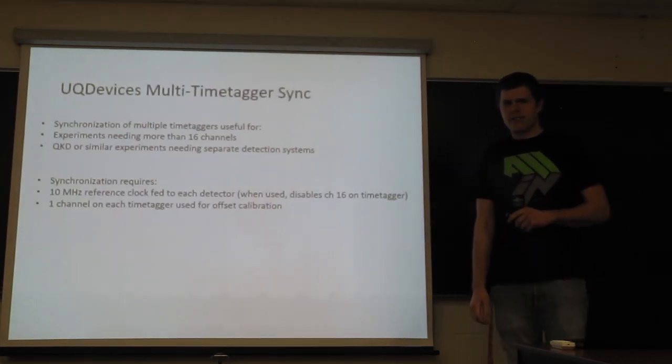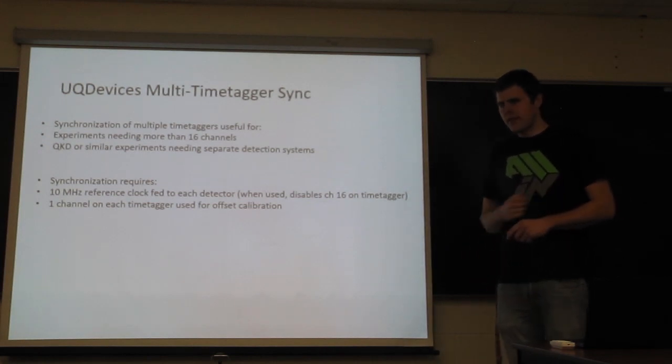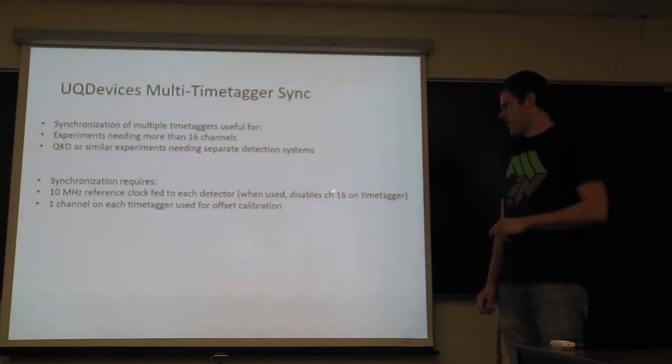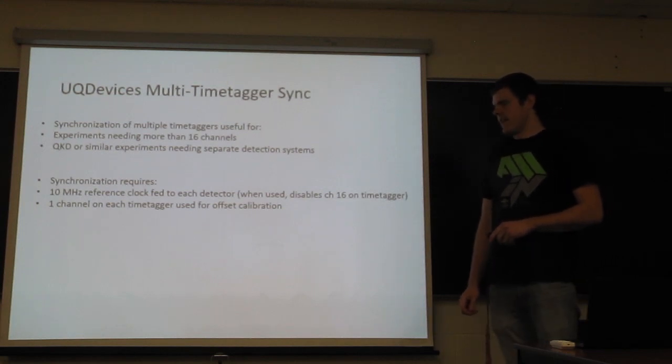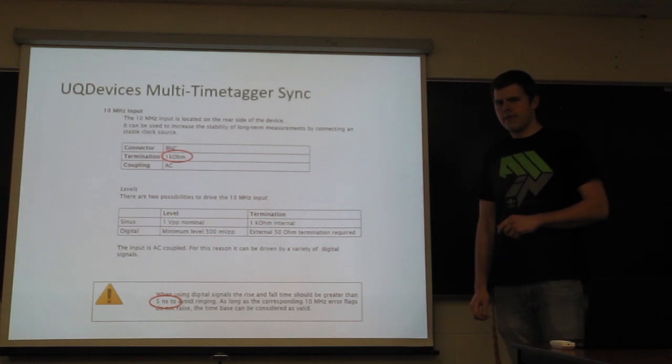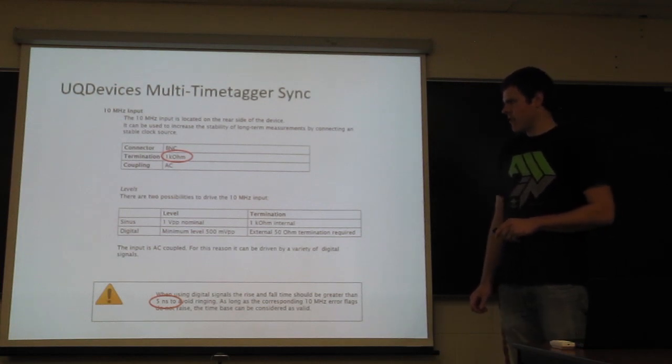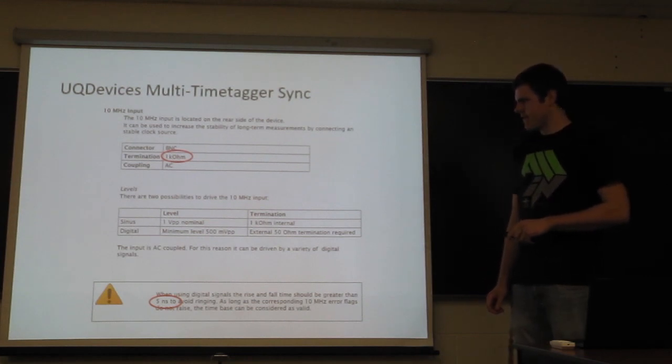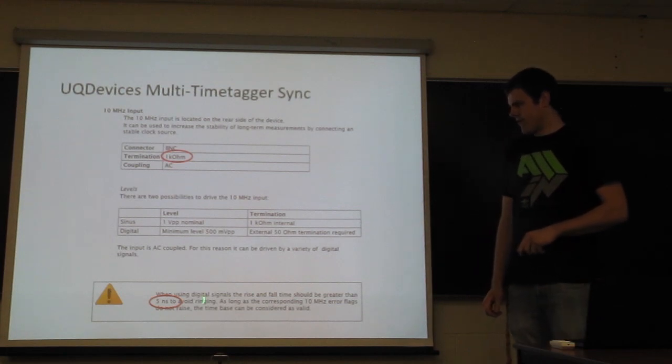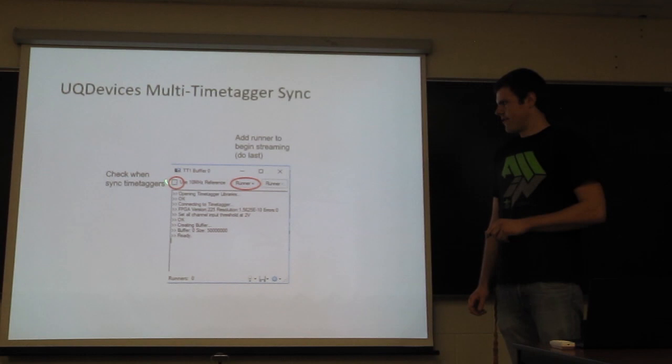Now, we're going to talk about synchronizing two time taggers. This is useful if you want to have a time tagger with more than 16 channels, and then also this can be used if you have two experiments where the detection systems need to be separate. So synchronization requires a 10 megahertz reference clock, which will end up using channel 16 on the time tagger. And then it also requires another channel to be reserved for an offset calibration. There are some things to keep in mind when you make this 10 megahertz reference clock. So keep in mind that the termination is one kilo ohm. There's a specification for what the voltage of the signal needs to be, and also the rise time cannot be too quick. So when you want to use a 10 megahertz reference, make sure you click this button before adding a run.